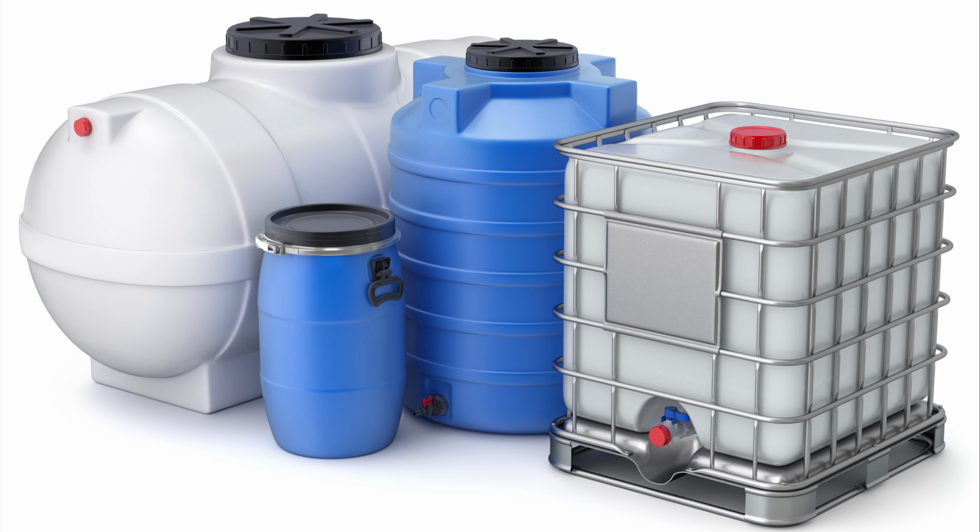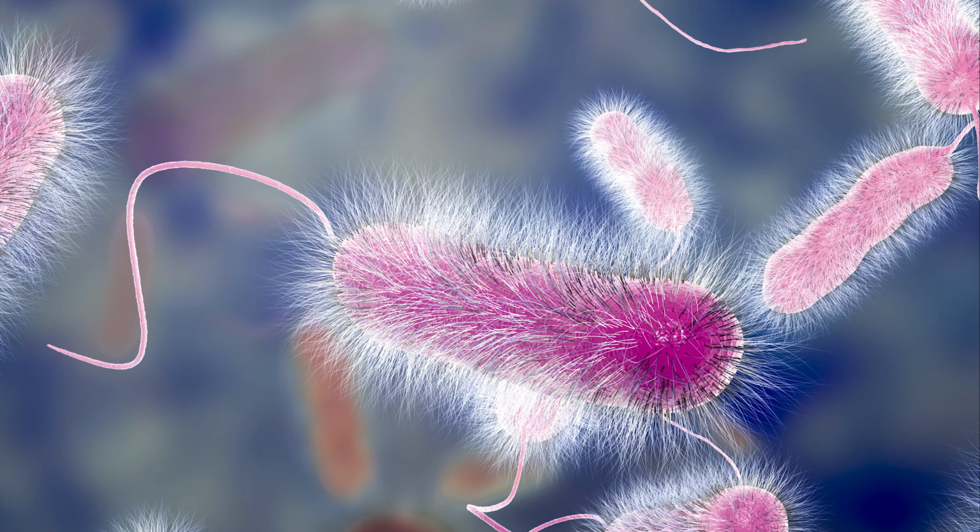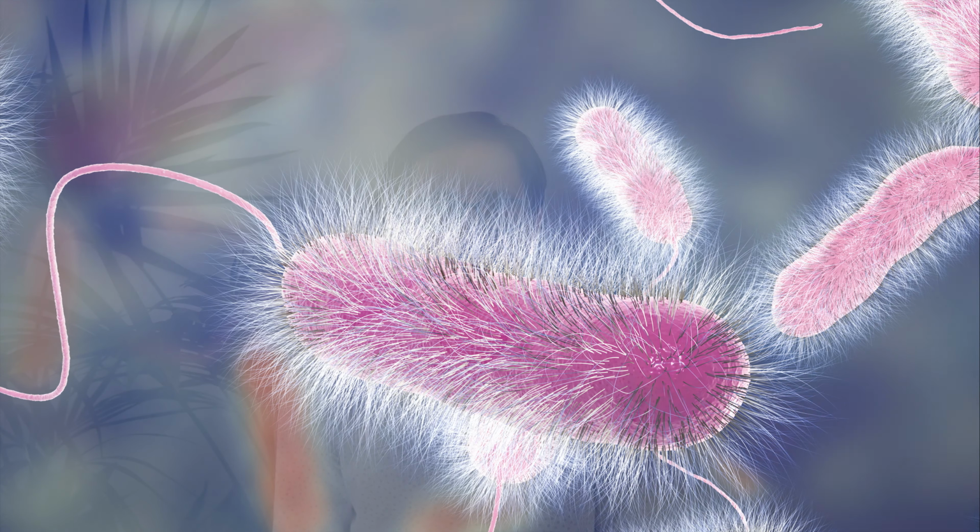Wherever heated water is stored at temperatures of around 20 to 40 degrees C, there is an increased risk of harbouring or proliferating legionella bacteria. These systems must therefore have controls in place to reduce any of these bacteria to safe levels. Most often this comprises an electric heater and a mixing pump to raise the water to a sufficiently high and uniform temperature. Alternatively, if this water cannot be increased in temperature, then a biocide can be used to serve the same purpose.